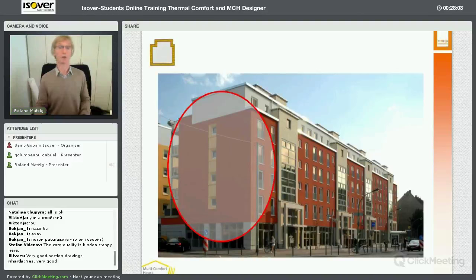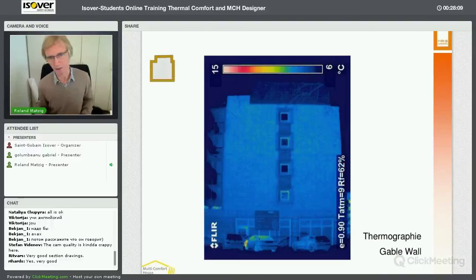Very important. On the north side, for example, we have hardly any windows in the wall. And this facade, for example, this is a thermal image, not thermal bridge, a thermal image of the facade in the wintertime, and you see only very, very small yellow areas, means this is all cold, which is perfect, and the yellow is not as perfect as it should be here and there a little bit. But this can be because the window was opened a few minutes before or so.